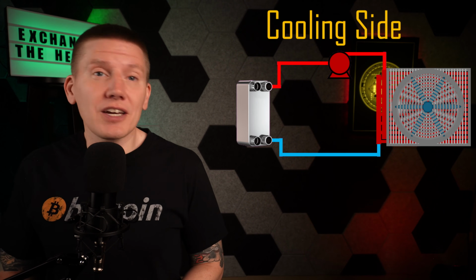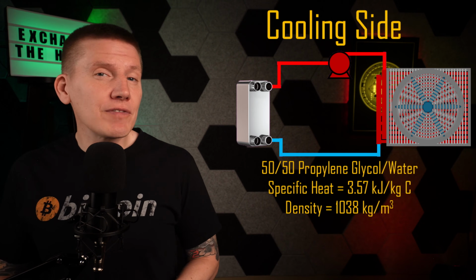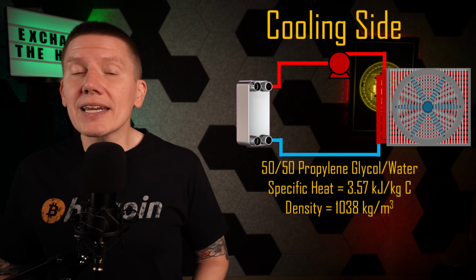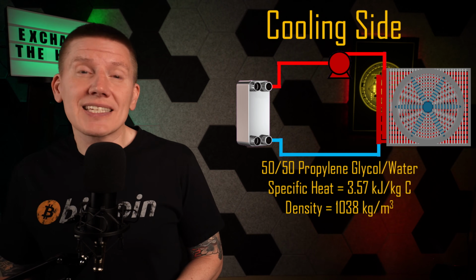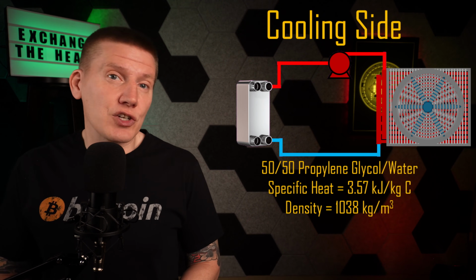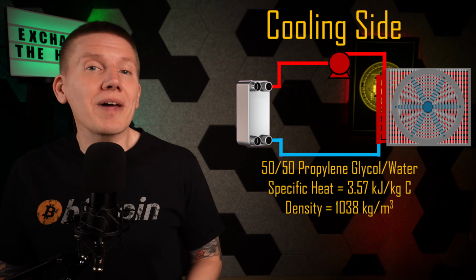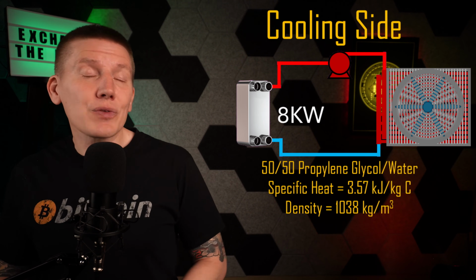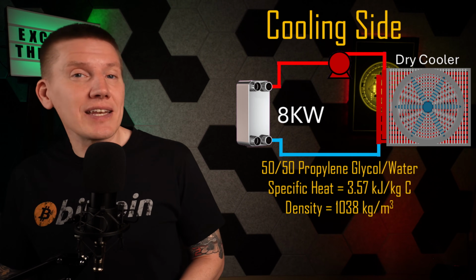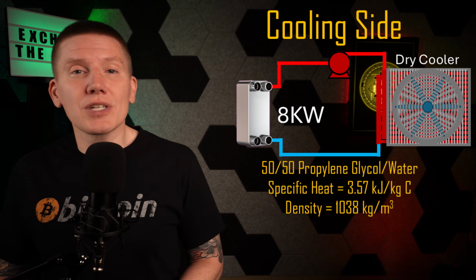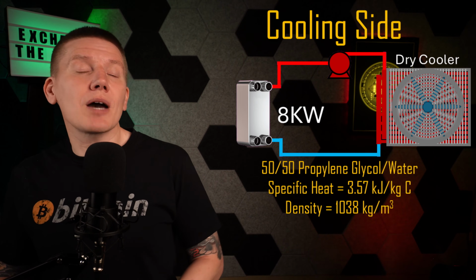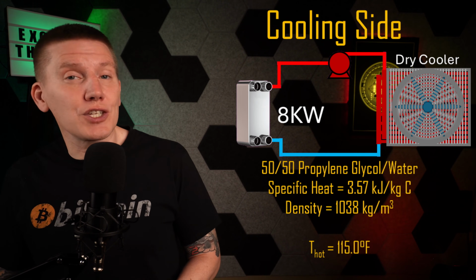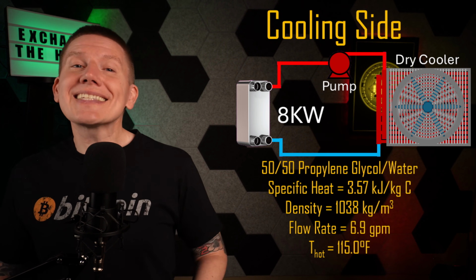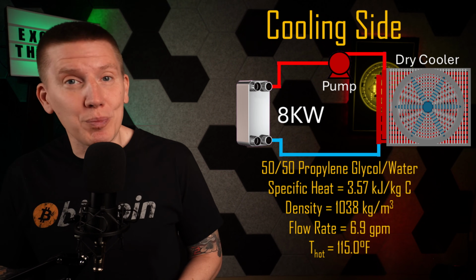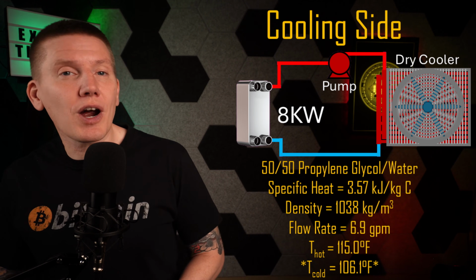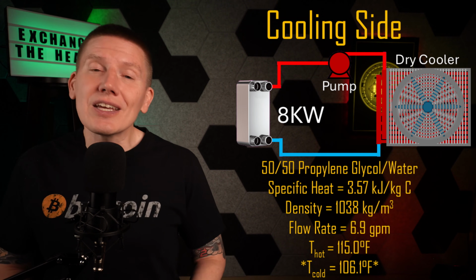Looking at the other side of the heat exchanger, maybe I've got a 50-50 mix of propylene glycol and water providing my cooling. Now, since the dielectric fluid is giving off 8 kilowatts of heat into the heat exchanger, the glycol water is going to have to absorb that same 8 kilowatts of heat. Now, let's say I have a dry cooler outside dissipating this heat to the open air, and it's the middle of summer on a really hot day. Maybe the fluid coming out of the heat exchanger is 115 degrees Fahrenheit, and maybe I've got a pump moving 6.9 gallons per minute through the cooling loop. Doing the math, this gives me a fluid temperature of around 106 degrees Fahrenheit going into the heat exchanger.